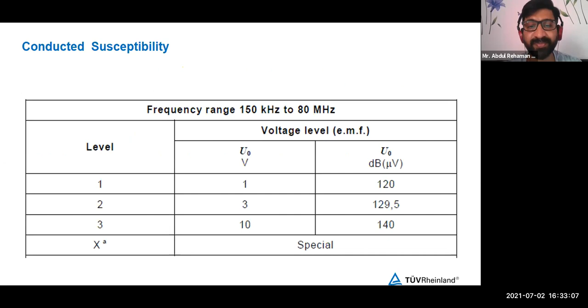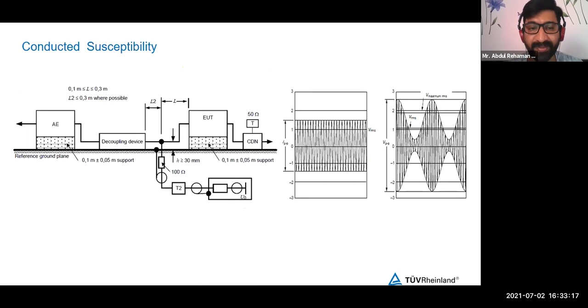This is the typical extract from the standard, where it is defined at what particular distance you inject the noise. It is for the frequency range from 150 kilohertz to 80 megahertz. It can be 3 volts, 10 volts, or 6 volts for ISM bands. And this modulation is 1 kilohertz, or 2 hertz for medical products; for 2 hertz, it is used for 80% modulation with a step size of 1%.